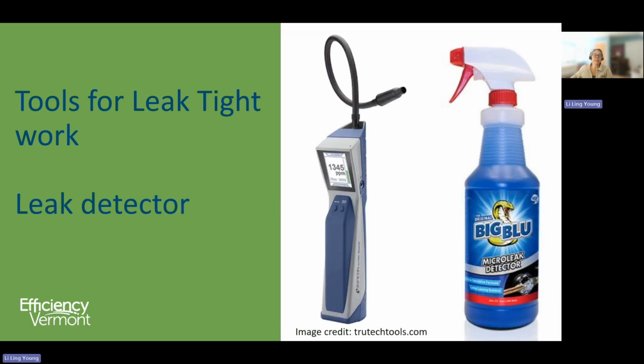Once the refrigerant piping is complete, check for leaks. Both an electronic leak detector and leak detection fluid are essential tools of the trade. Yes, lots of techs swear by dish soap as a leak detection fluid, but some dish soaps are corrosive, and non-corrosive fluid specifically formulated for leak detection on copper is best practice.